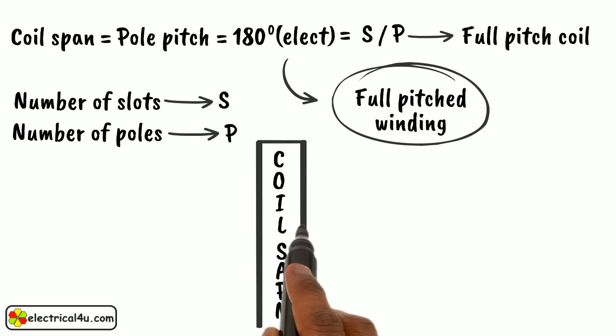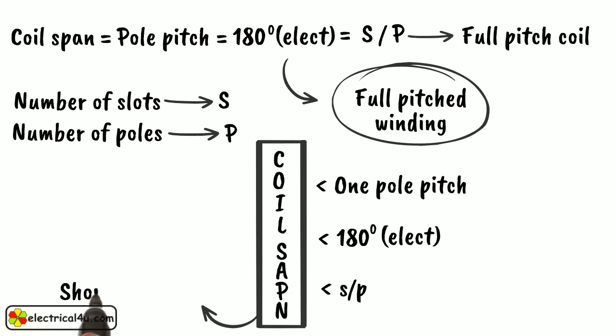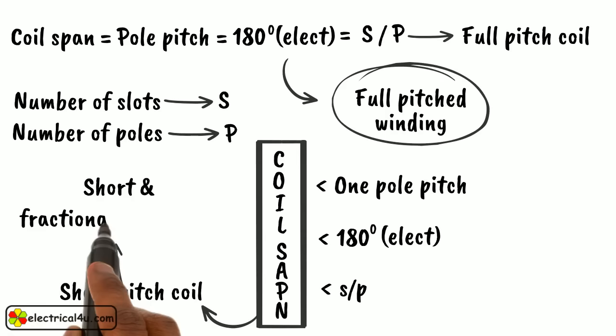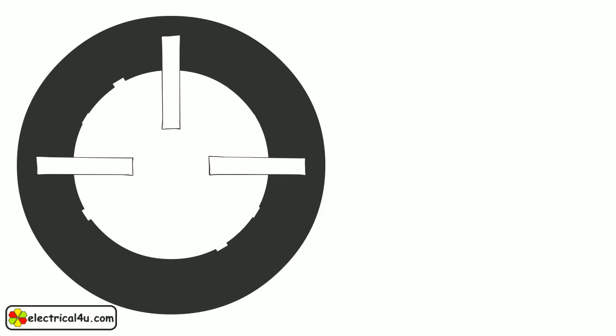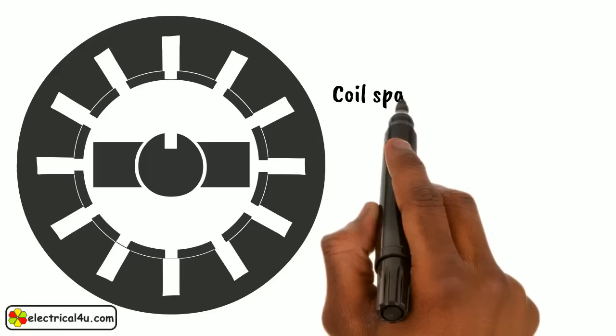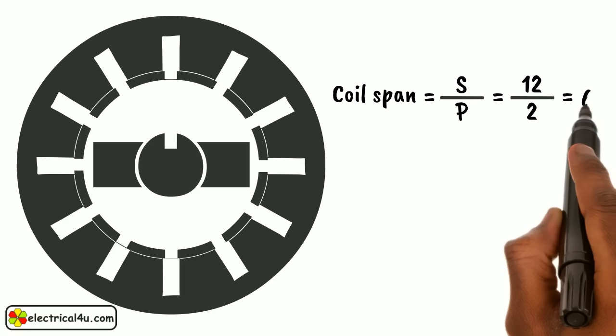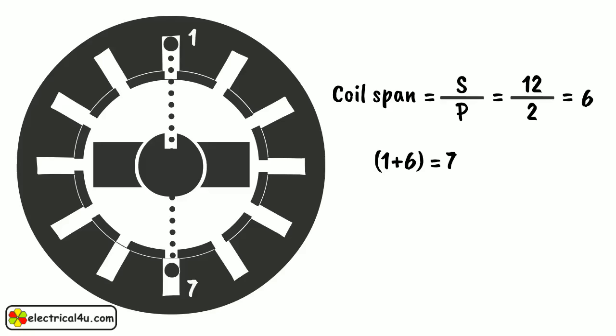If the coil span is less than one pole pitch, that is less than 180 degree electrical or less than the number of slots per pole, then it is called a short pitch coil and the complete winding is called as short pitch winding or fractional pitch winding. For example, consider a three phase, two pole, twelve slot alternator. The coil span for full pitched winding is equal to s by p, that is twelve by two which is six. So if one side of the coil is placed in slot one, then the other side of the coil must be placed in slot one plus six, or seven.